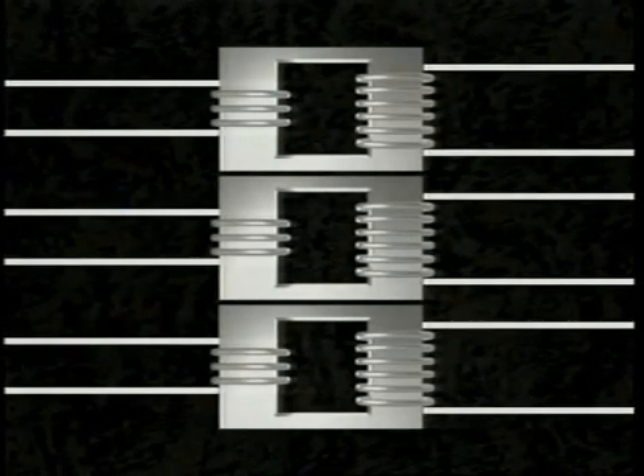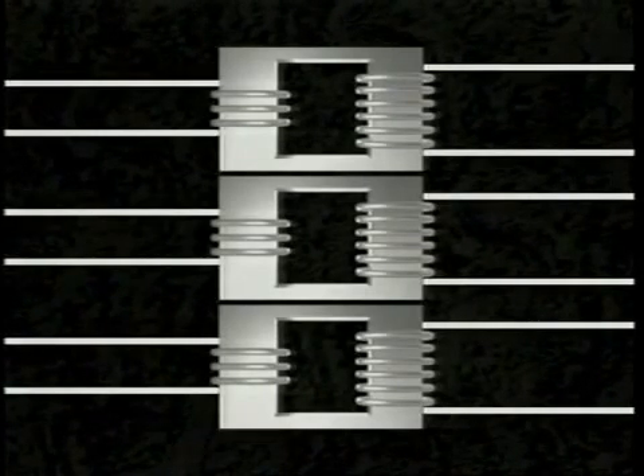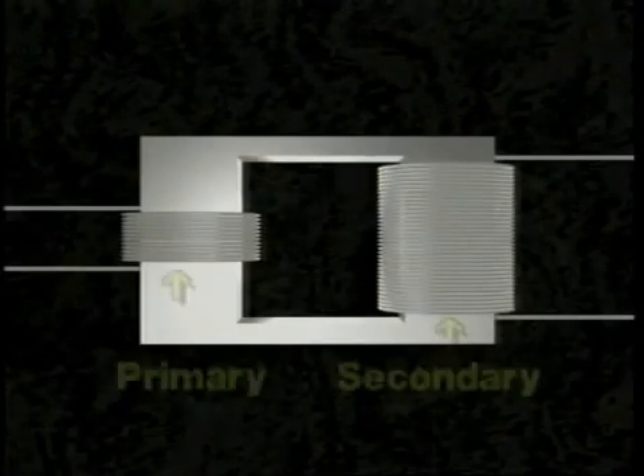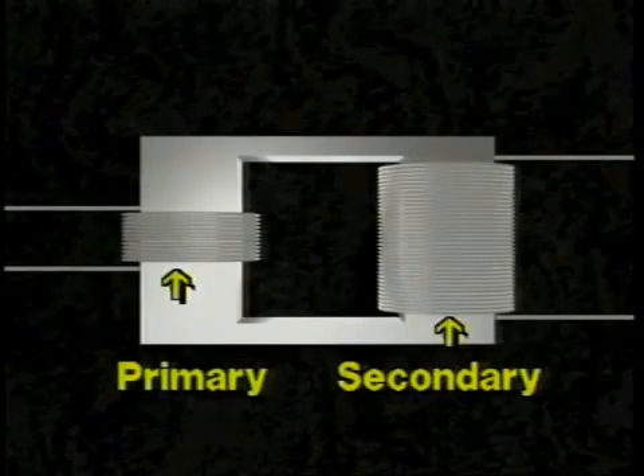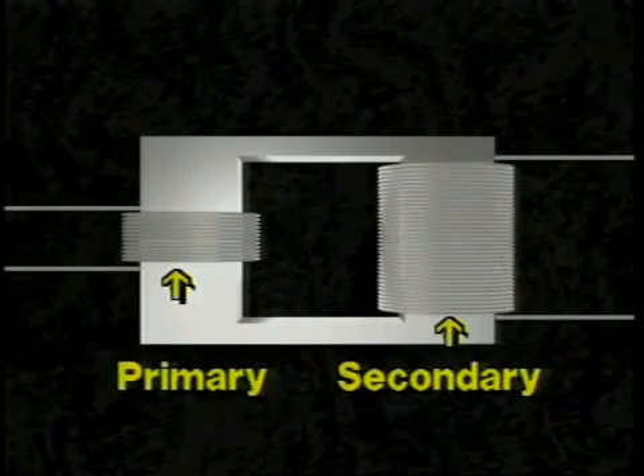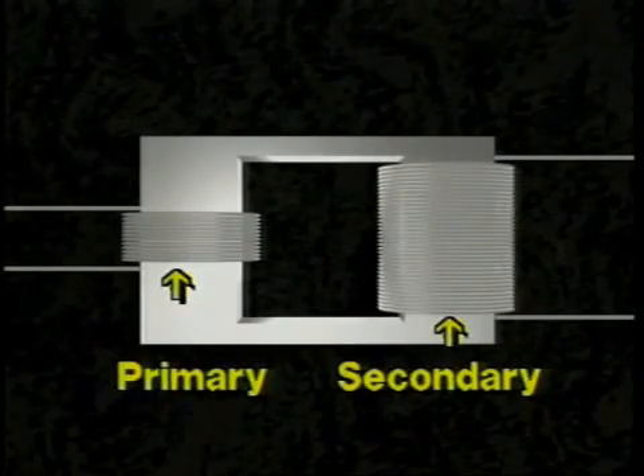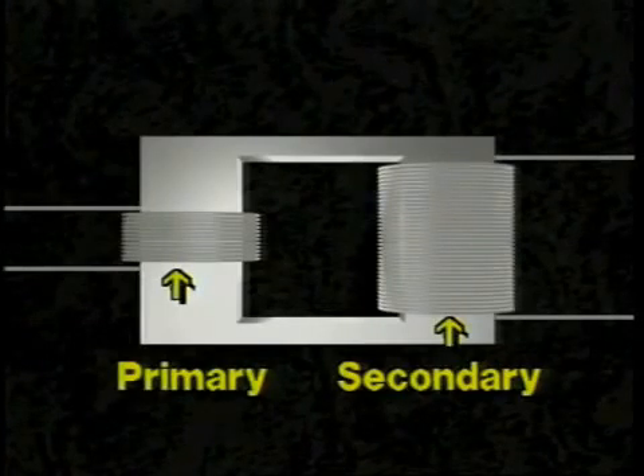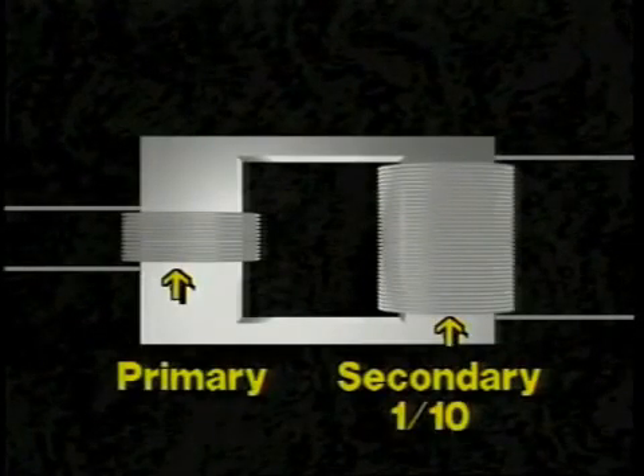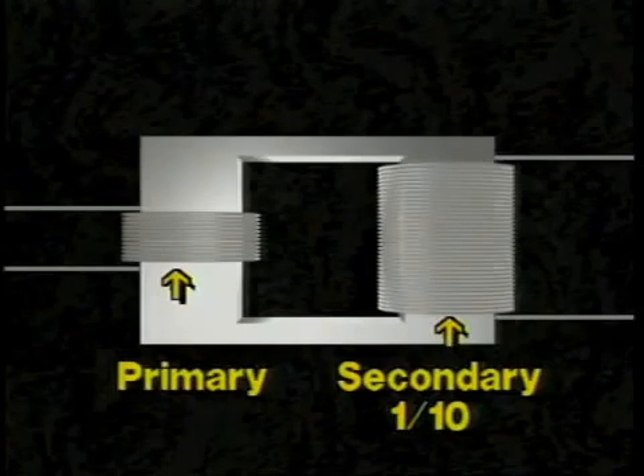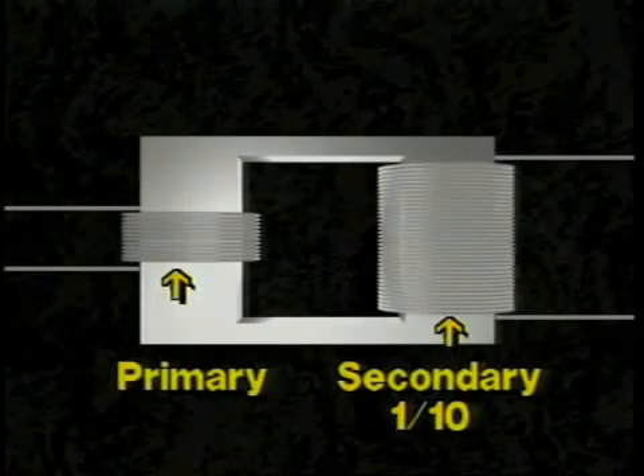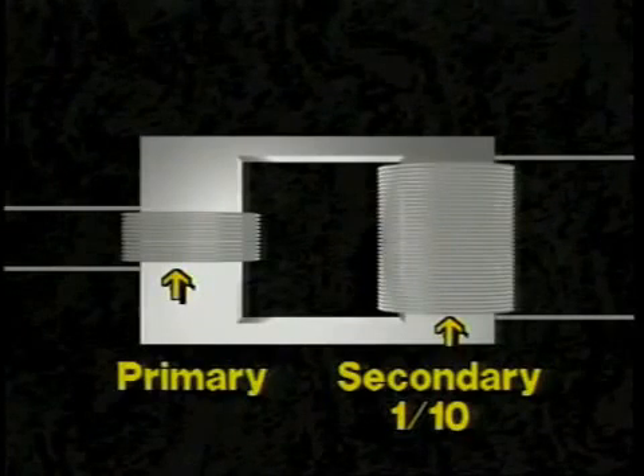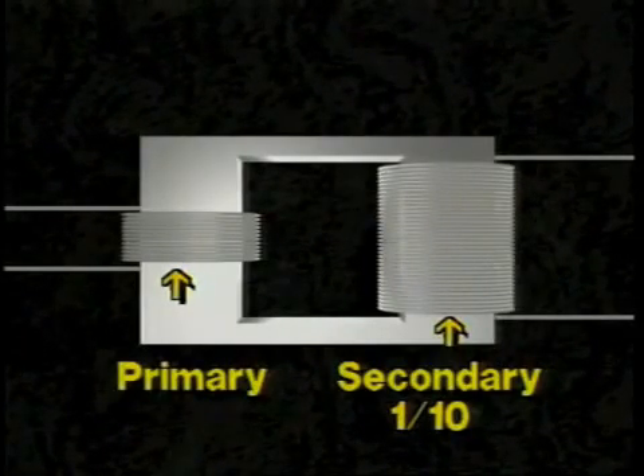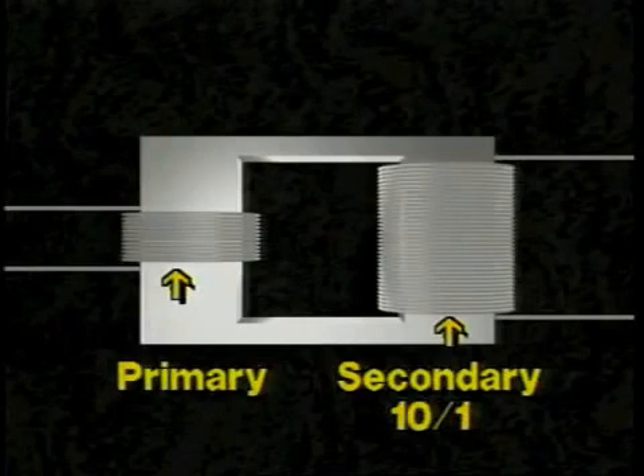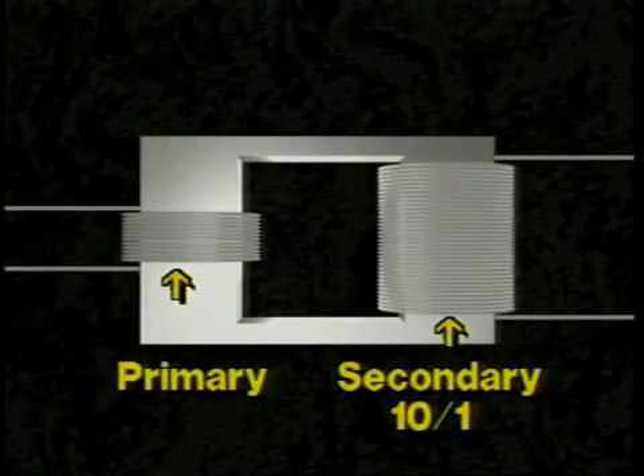The voltage change is determined by the ratio of the number of turns on each side. In this example of a step-up transformer, the primary side of the transformer has 100 turns and is fed by a 120-volt AC power source. The secondary side has 1,000 turns, a ratio of 1 to 10 for each phase. The voltage rating of the secondary side is 1,200 volts. For a step-down transformer, the ratio would be reversed, that is, a 10-to-1 ratio.